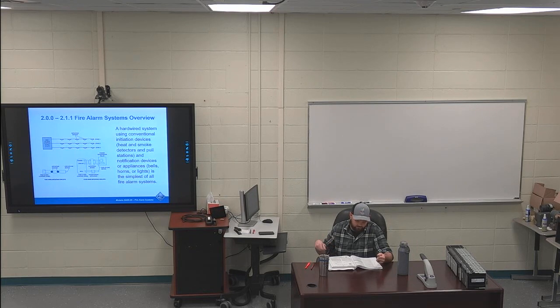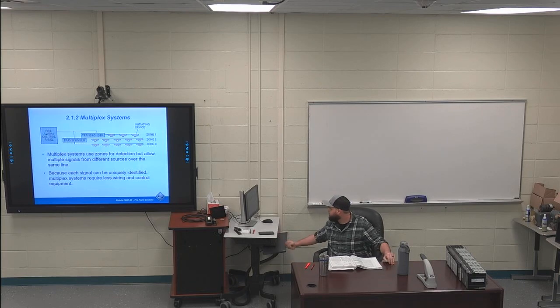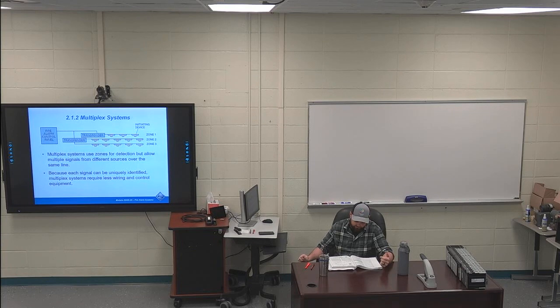That's a little bit more intensive system. Multiplex systems, 212. I've got the first couple of sentences of 212 highlighted. Multiplex systems are similar to hardwired systems in that they rely on zones for fire detection. The difference, however, is that multiplexing allows multiple signals from several sources to be sent and received over a single communication line.